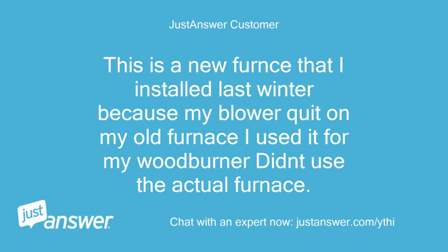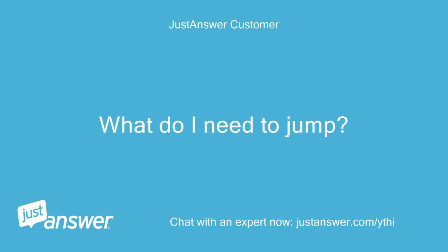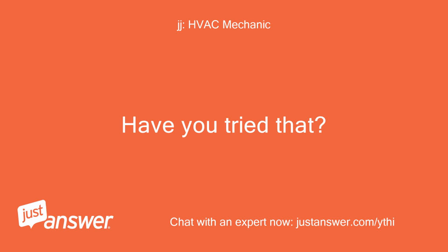This is a new furnace that I installed last winter because my blower quit on my old furnace. I used it for my wood burner, didn't use the actual furnace. I have both thermostats shut off and the blower keeps running. What do I need to jump? The blower running is a separate issue. It may be the fan switch at the thermostat is set to on. Have you tried that?